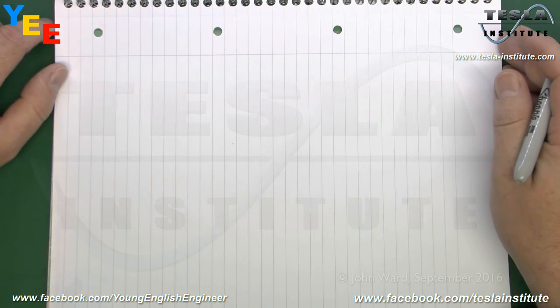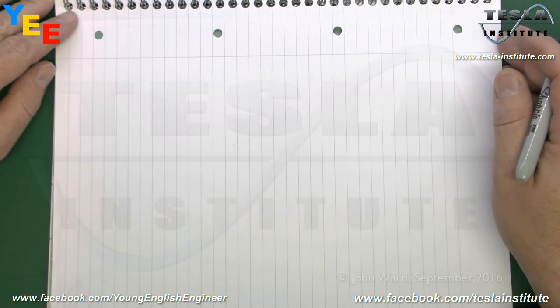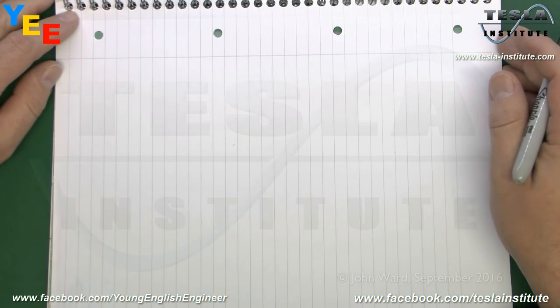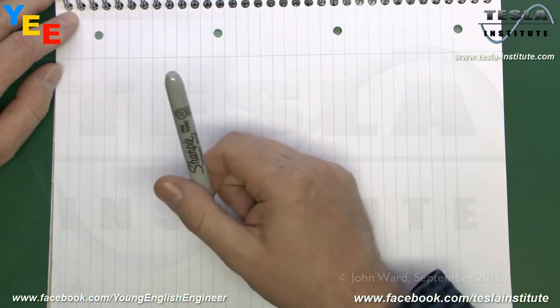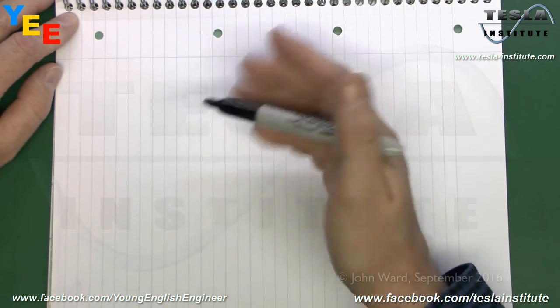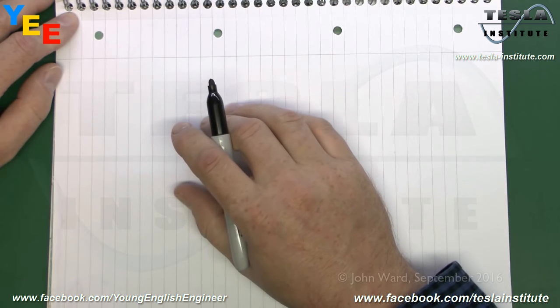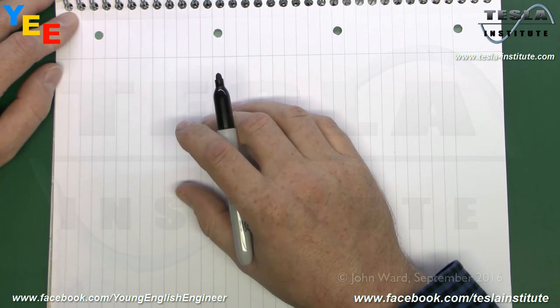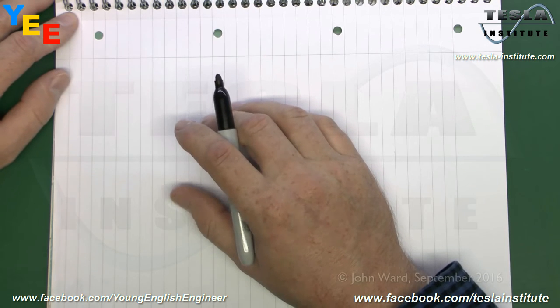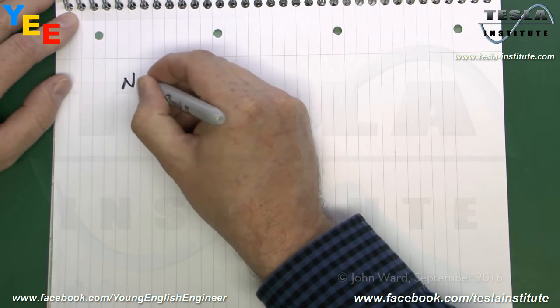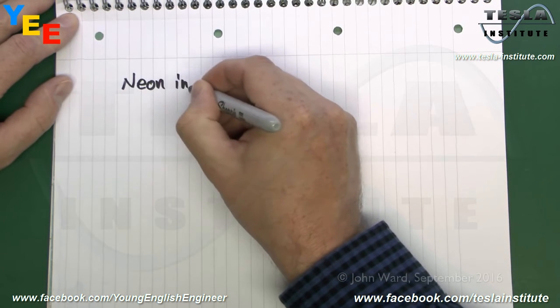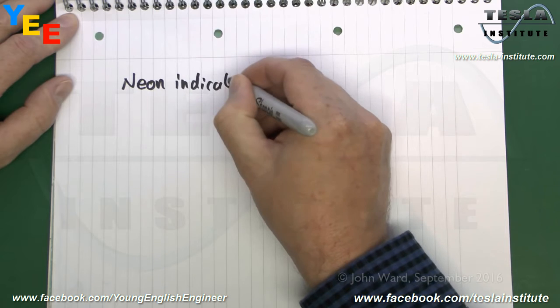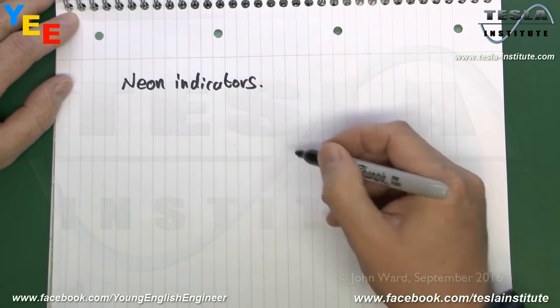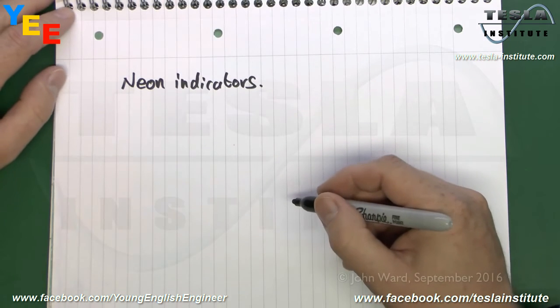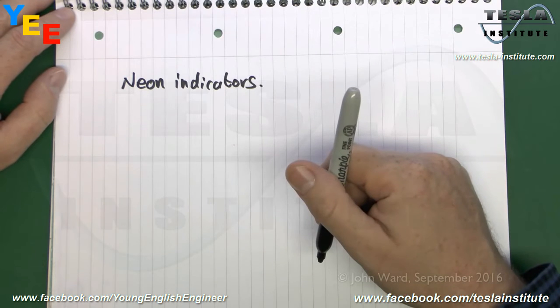Now, there is another thing to look out for, which can give somewhat misleading results, and it's where you have, say, a fused connection unit or an isolator switch, and this could be for a kitchen appliance, or one of those pull cords for an electric shower. And a lot of these switches have neon indicators in them. And those are little orange things that light up when the switch is in the on position to basically show that the thing is powered.